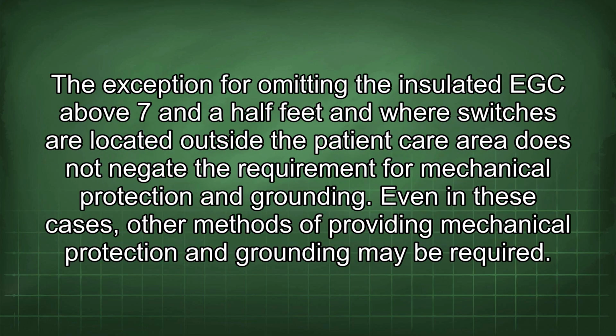The exception for omitting the insulated EGC above 7.5 feet and where switches are located outside the patient care area does not negate the requirement for mechanical protection and grounding. Even in these cases, other methods of providing mechanical protection and grounding may be required.